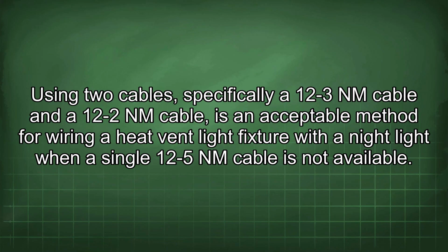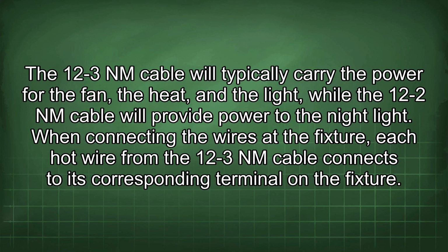Using two cables, specifically a 12-3 NM cable and a 12-2 NM cable, is an acceptable method for wiring a heat vent light fixture with a night light when a single 12-5 NM cable is not available. The 12-3 NM cable will typically carry the power for the fan, the heat, and the light, while the 12-2 NM cable will provide power to the night light.